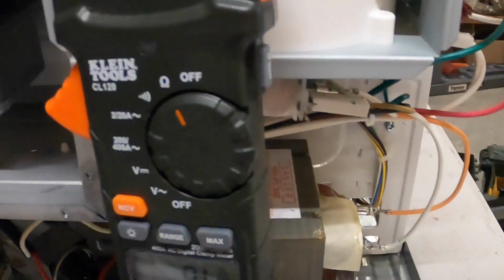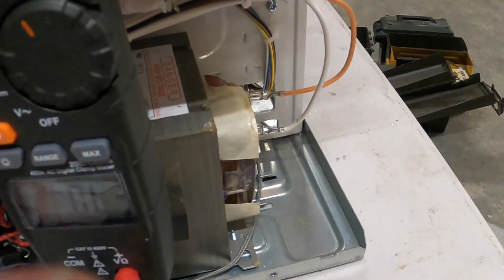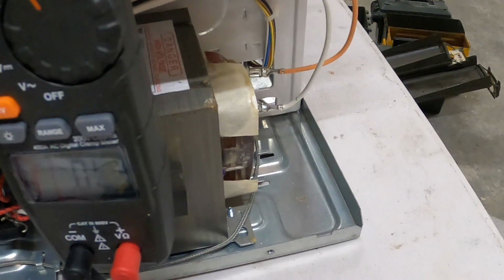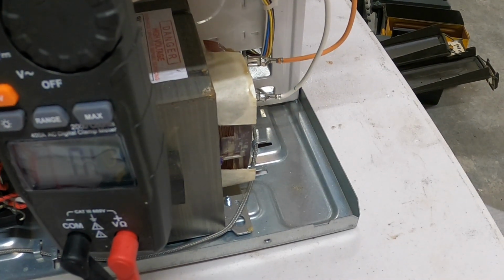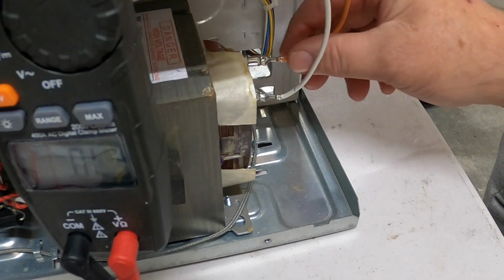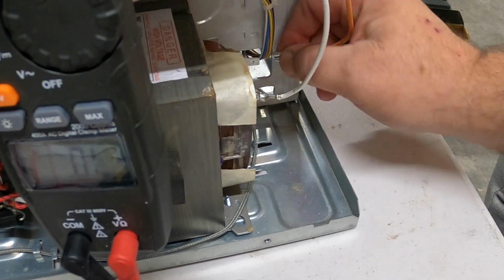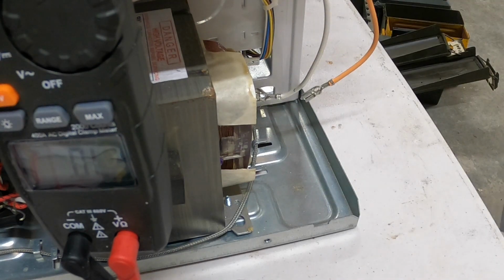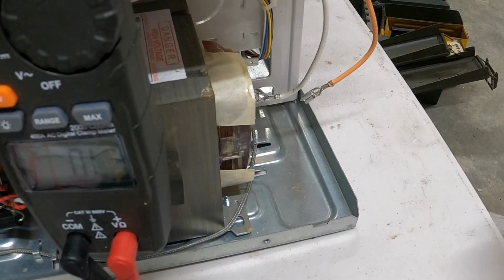So we'll start with your high voltage transformer. I showed in a previous video checking for power to the transformer, but every so often you'll have a bad transformer, one that opens up. So we pull one lead and check for continuity. Always pull one lead off, or you'll get false readings.